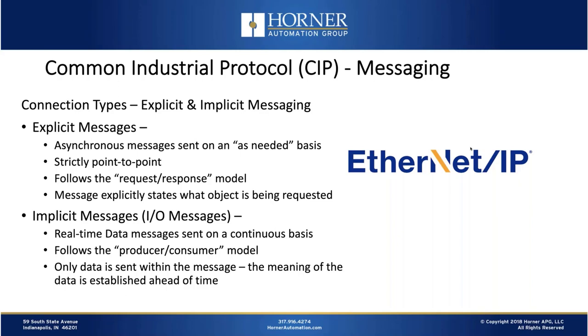Implicit messages, most often called I/O messages, are real-time data messages sent on a continuous basis. They follow the producer-consumer model and could be unicast one-to-one, multicast one-to-many, or potentially broadcast. Only data is sent within the message, meaning the meaning of the data is established ahead of time — the full definition of what data is desired is not contained inside the message, so it's implicit and established ahead of time.